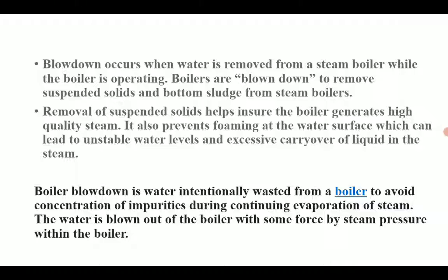This can be a continuous process or an intermittent process. You can continuously remove some water at the bottom, or you can remove it every 5 minutes or 1 hour, like that. Boiler blowdown is water intentionally wasted from a boiler to avoid concentration of impurities during the continuing evaporation of steam. The water is blown out of the boiler with some force by steam pressure within the boiler.